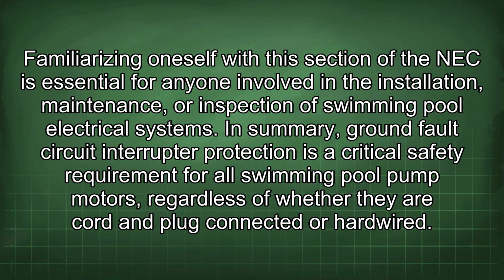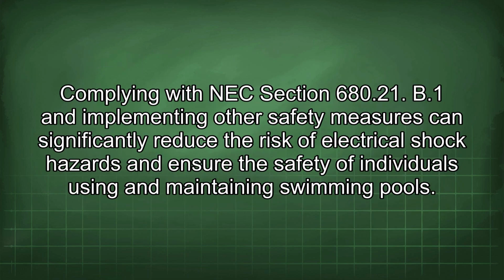In summary, ground fault circuit interrupter protection is a critical safety requirement for all swimming pool pump motors, regardless of whether they are cord and plug connected or hardwired. Complying with NEC Section 680.21 B.1 and implementing other safety measures can significantly reduce the risk of electrical shock hazards and ensure the safety of individuals using and maintaining swimming pools.